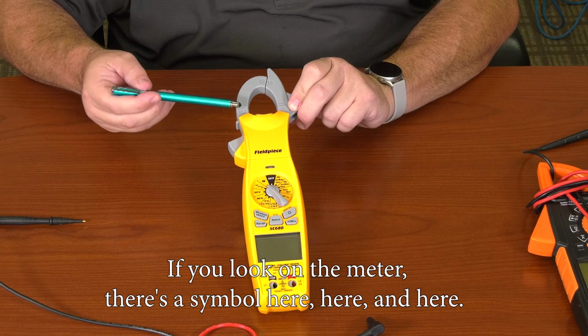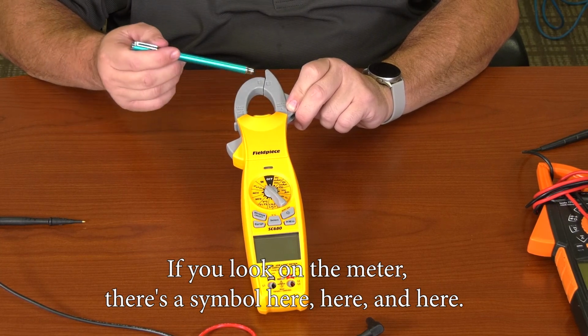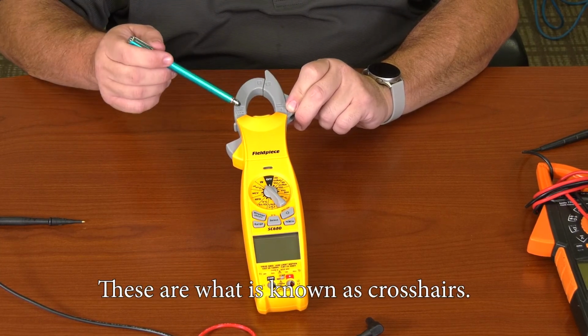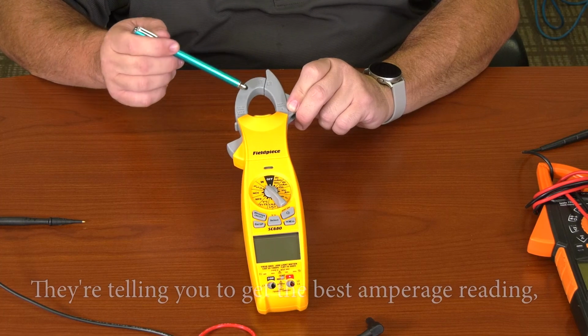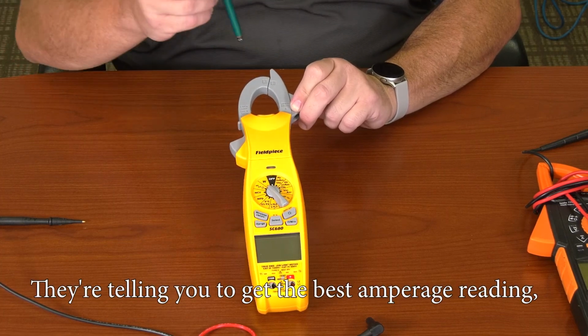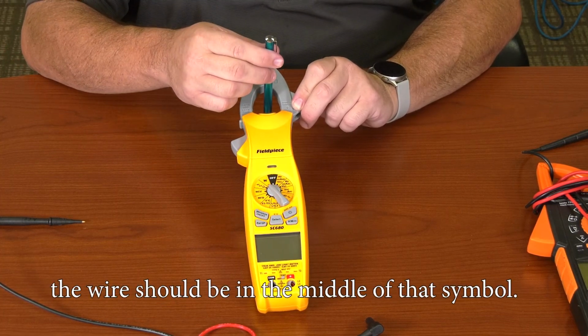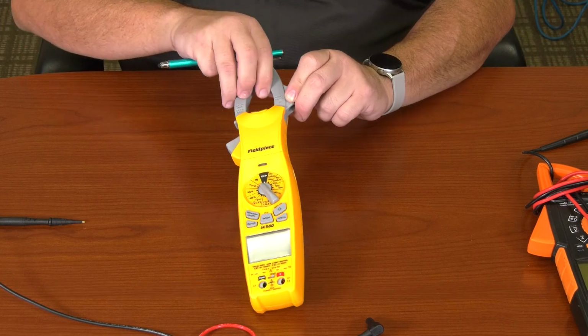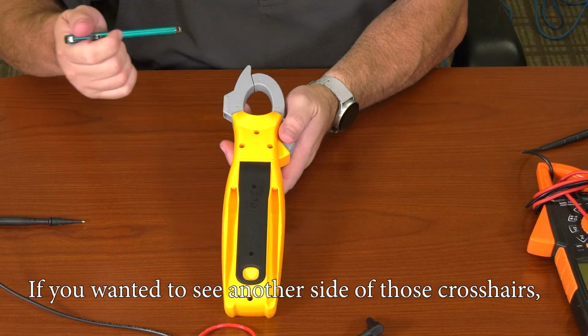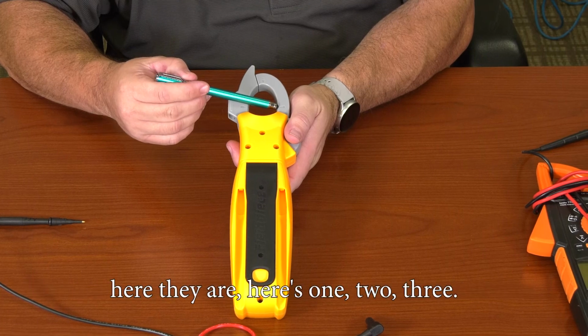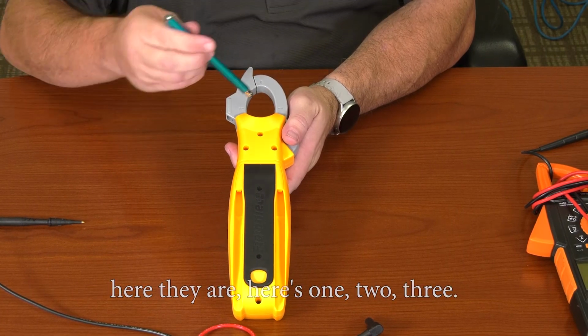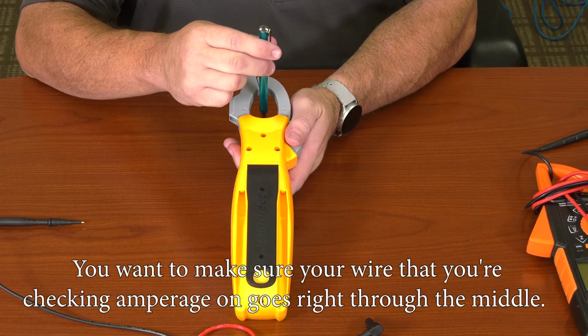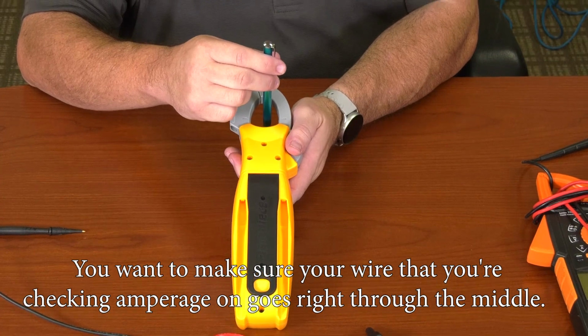If you look on the meter, there's a symbol here, here, and here. These are what is known as crosshairs. They're telling you to get the best amperage reading, the wire should be in the middle of that symbol. Okay. So that's one of the meters that we look at. If you wanted to see another side of those crosshairs, here they are. Here's 1, 2, 3. You want to make sure your wire that you're checking amperage on goes right through the middle.